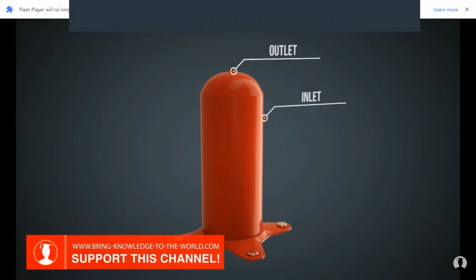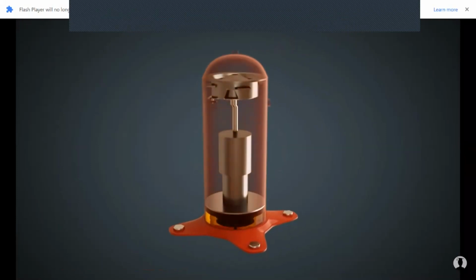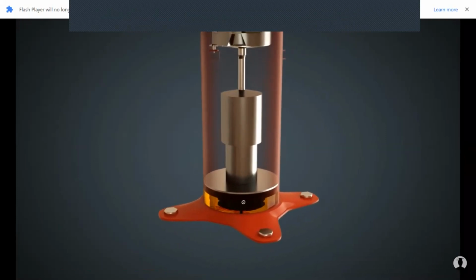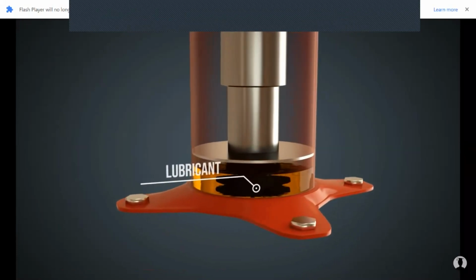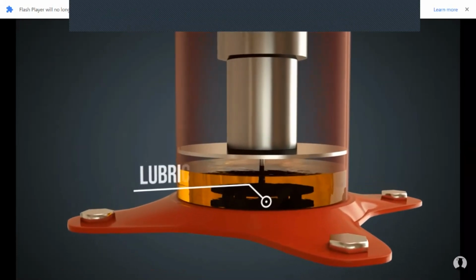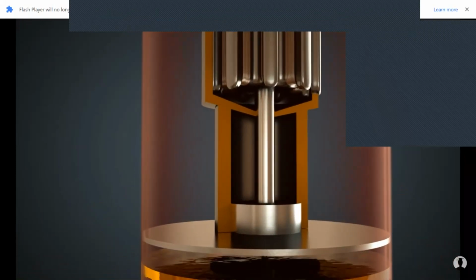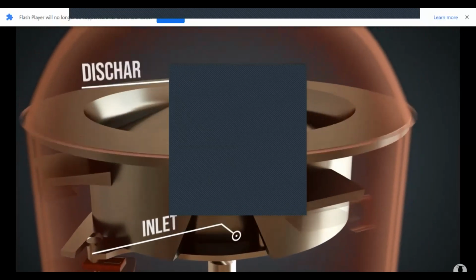A scroll compressor is also known as a scroll pump and consists of a shell with an in and an outlet. The lower part of the shell contains the lubricant, which is used, for example, to lubricate the plain bearings. A motor sets an Archimedean scroll, which is found in the upper part of the shell, in motion. The scroll housing has an inlet, as well as a discharge port, and a fixed scroll. Here, the scroll housing is made transparent. The scroll housing has a base plate. The fixed scroll is attached to the underside of this base plate.